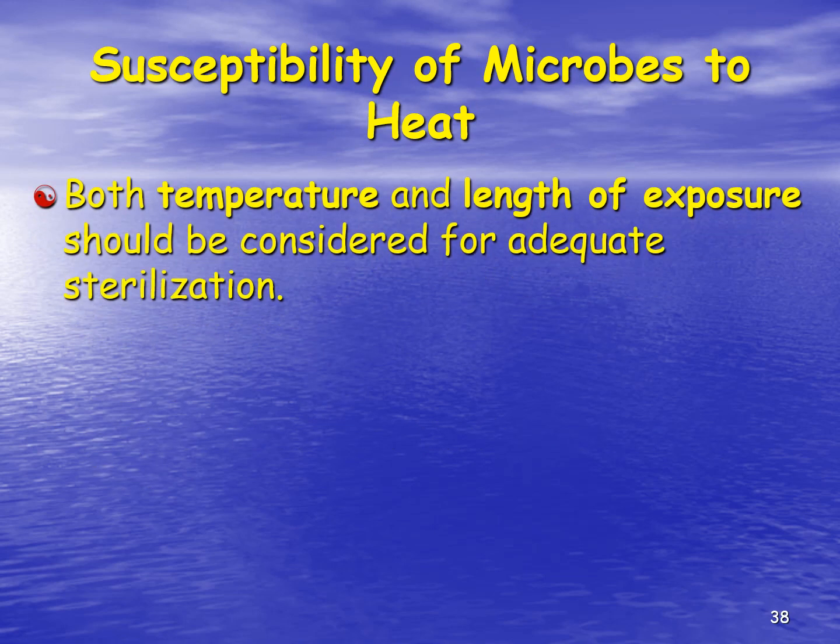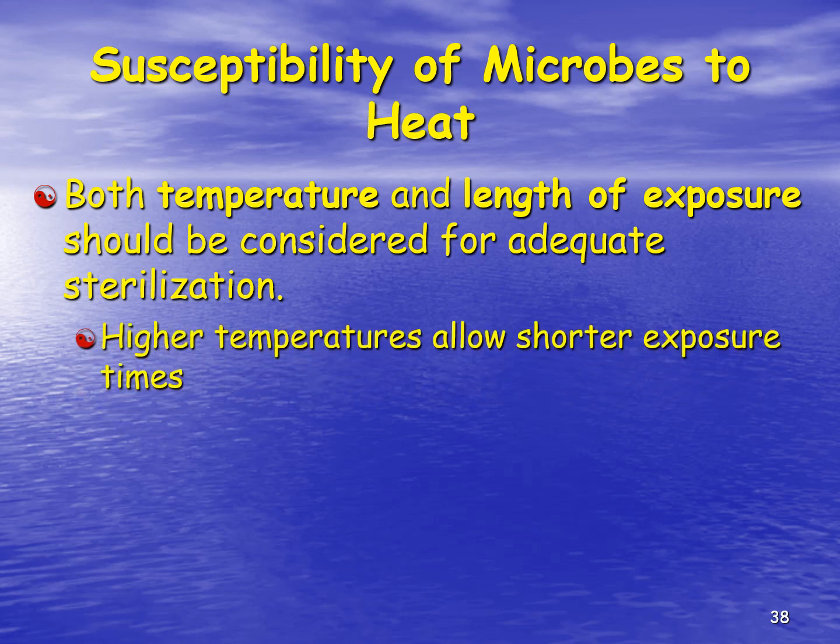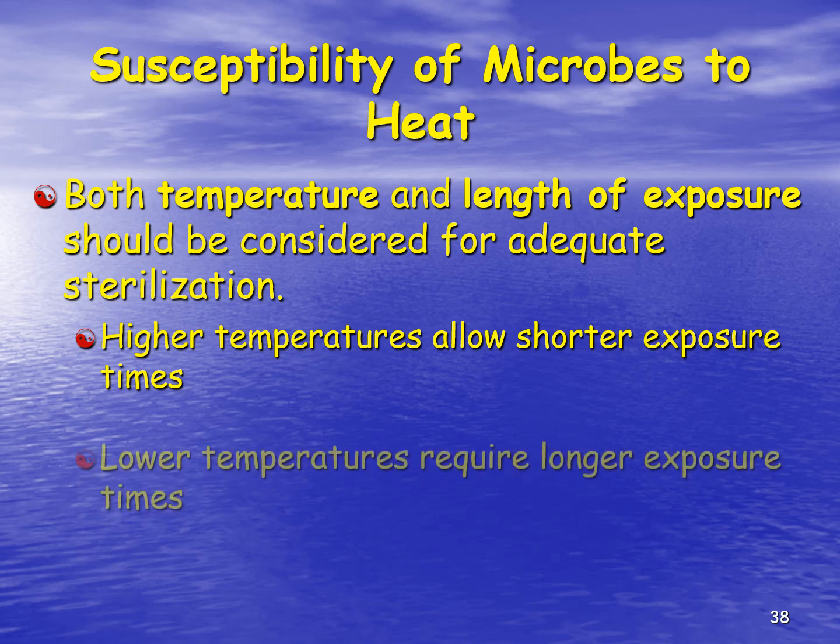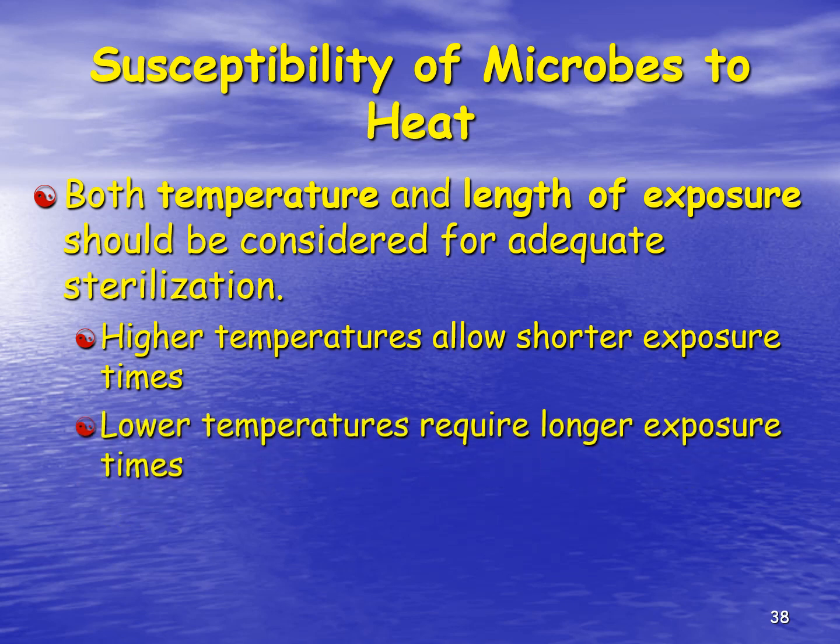Both temperature and length of exposure, therefore, should be considered for adequate sterilization. Higher temperatures allow for shorter exposure times. So therefore, lower temperatures are going to require longer exposure times. I could actually use my oven in my kitchen as a sterilizer, but it's going to take a long time to sterilize everything.